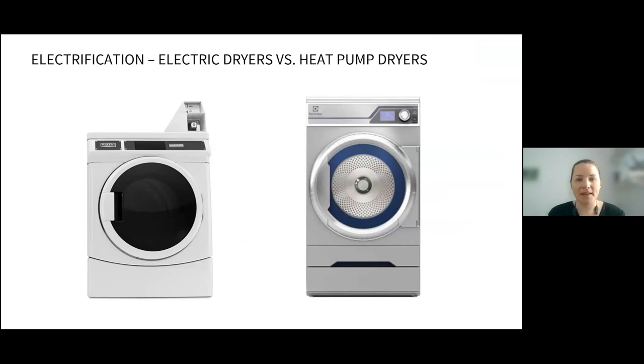Typically our affordable housing developer partners rent laundry equipment from a vendor who then also services them. So unfortunately right now, there are no vendors that provide heat pump dryers. This is unfortunate because heat pump systems would save us significant energy. On the decal project, for example, that means a difference of 7,400 kilowatt hours a year, which is also a large number because the electric resistance dryers produce a lot of internal heat gain that we have to then cool.